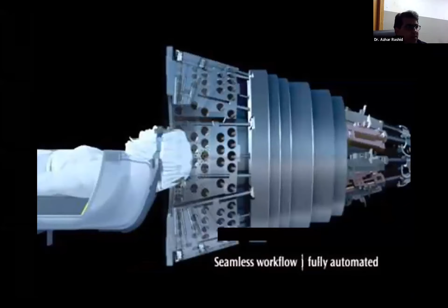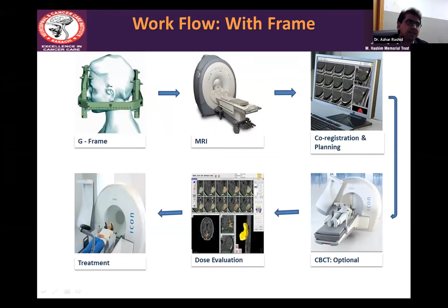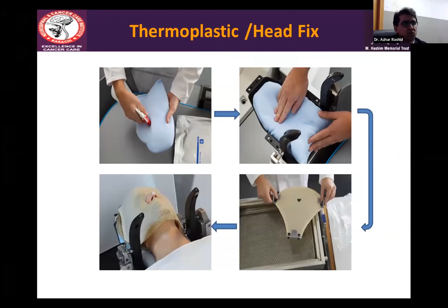This is the workflow. You apply the frame if you want the frame treatment, then get an MRI, co-registration and planning. It is optional to get CBCT with the frame. Usually we are not getting that one. Historically, we are treating with the frame and not getting CBCT, then dose evaluation and treatment. But with the thermoplastic sheet, which is a new development on gamma knife units, multi-session treatment can be done. If we use thermoplastic sheets, then we apply the thermoplastic, get an MRI, co-register, and then CBCT is a must, and then dose evaluation and then the treatment. This is a simple thermoplastic sheet which we usually use in the radiotherapy departments.